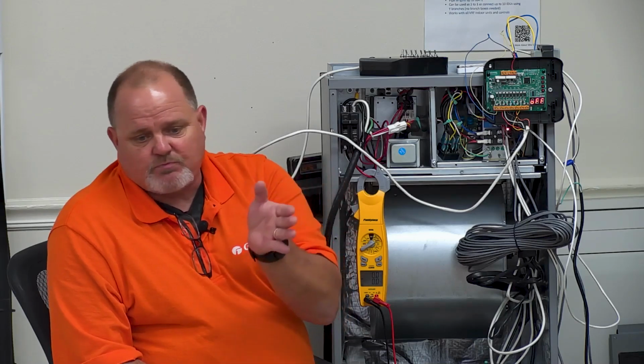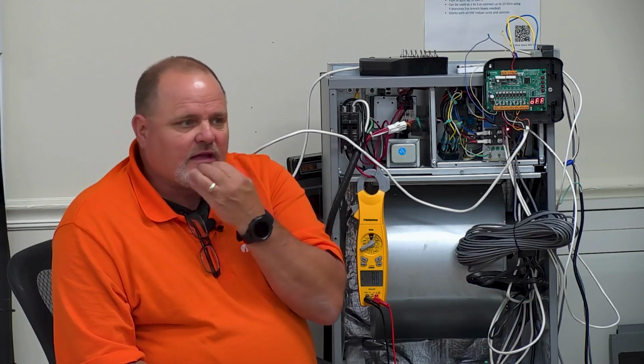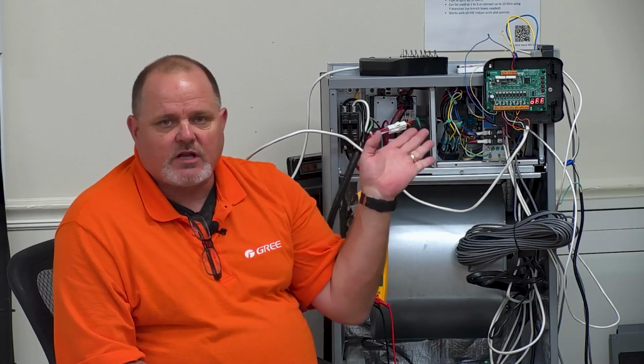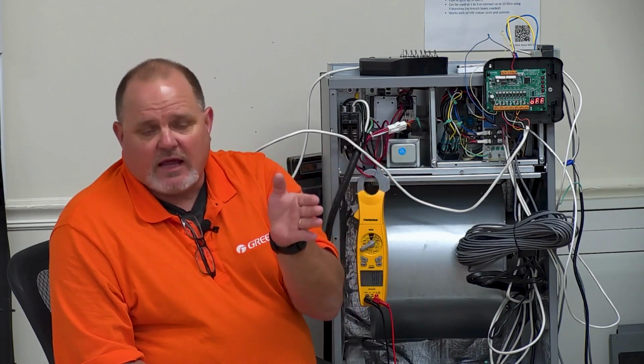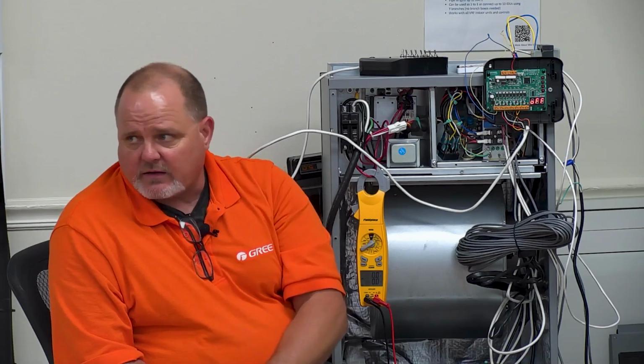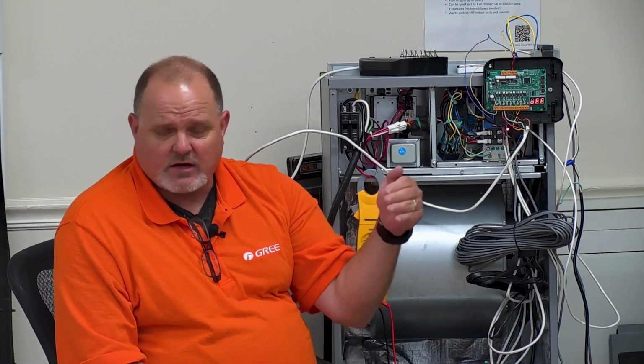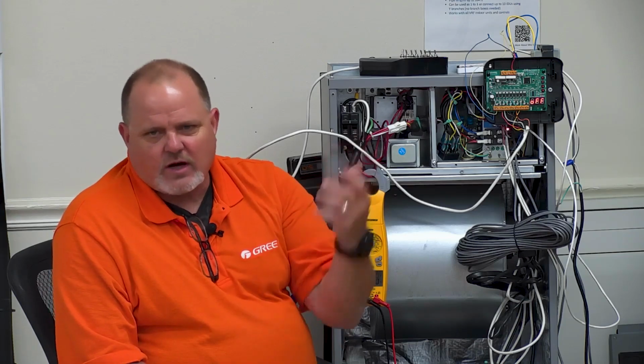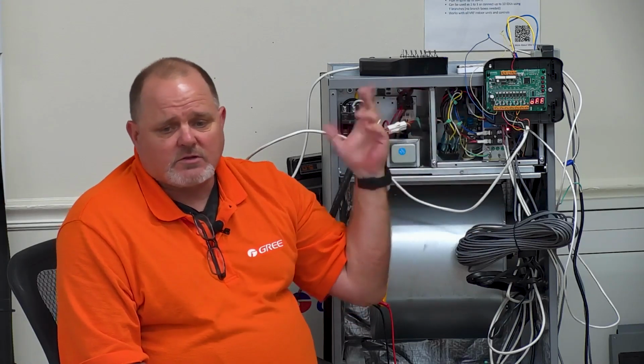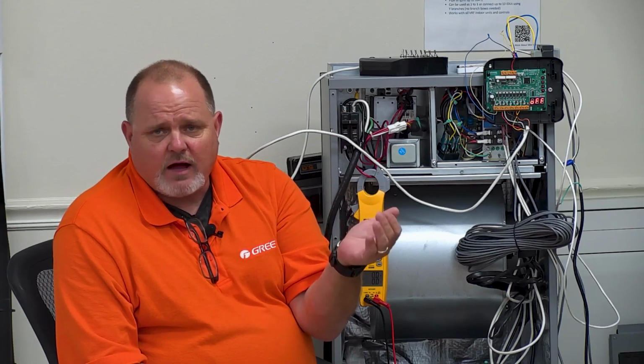If you're running like 0.6, 0.7, 0.8, then I would probably set that static pressure setting at like 6 or 7, and maybe even 8 if I'm running like a 0.9 static. Now, if you still can't get that static to drop by increasing your static curve, then you probably need to loosen up your ductwork, filters, something else is giving you the high static across that air handler, and just cranking that up is not really helping you much. So let's say we get it on high speed and we measure the static and my total static's like 0.02 or 0.2, I mean. Then you probably don't want to be at the static pressure setting of 5. You need to slow the thing back a little bit. So maybe set it like 3.